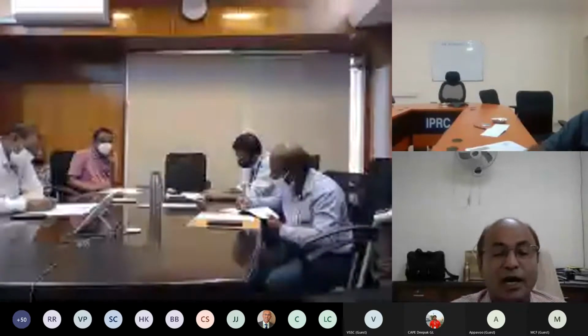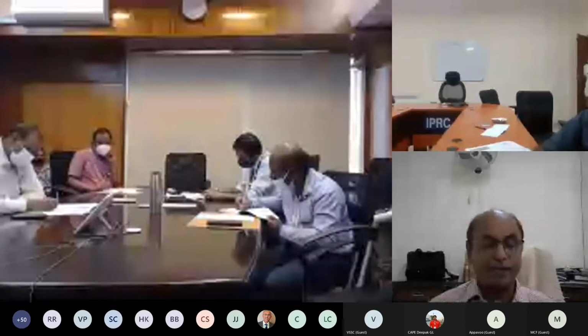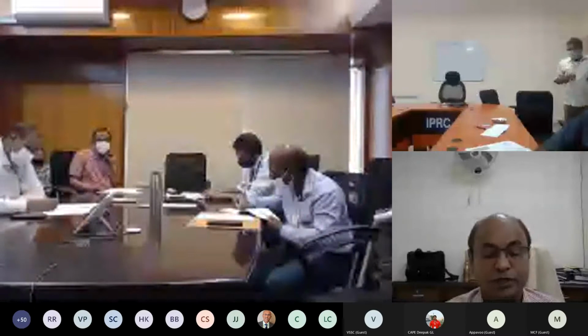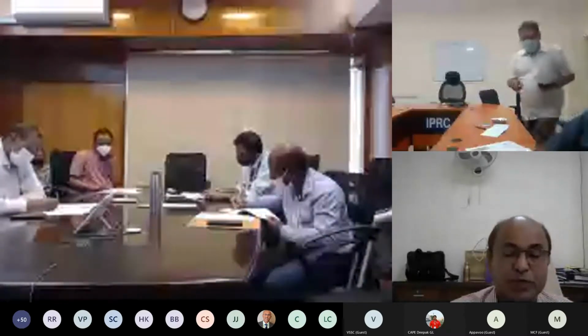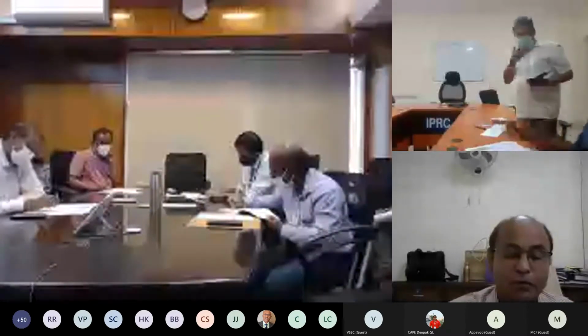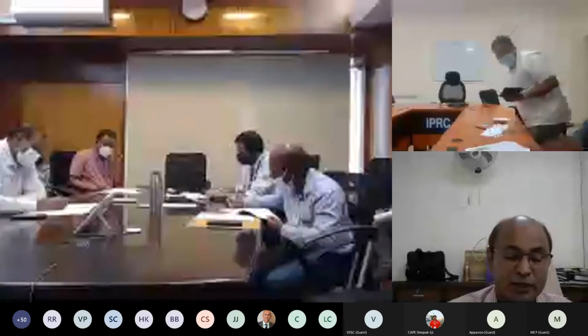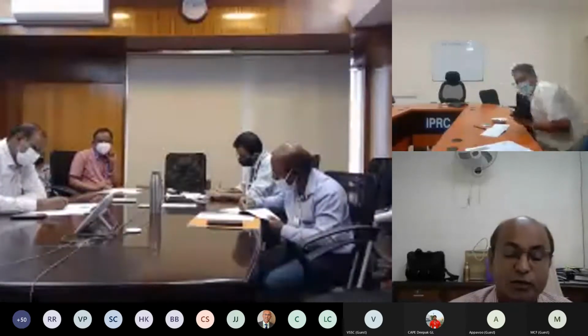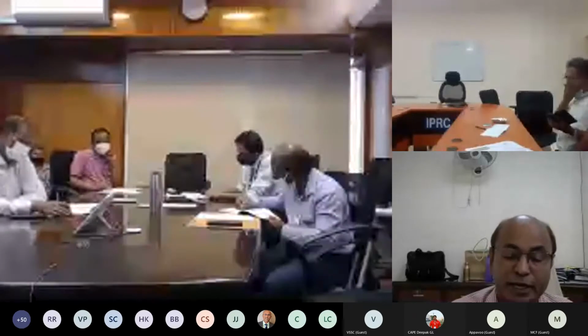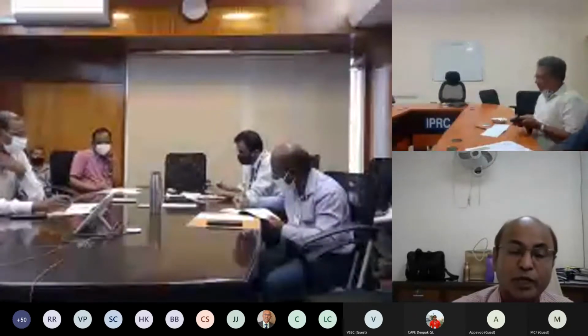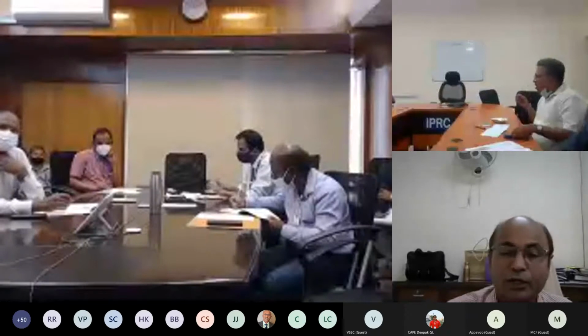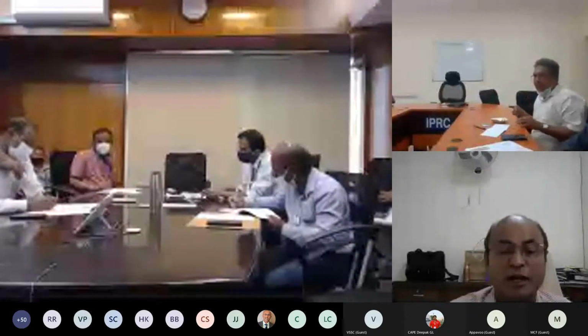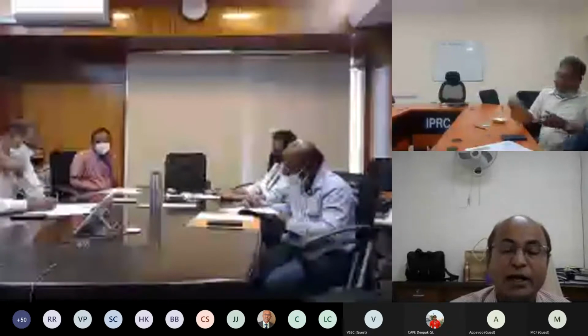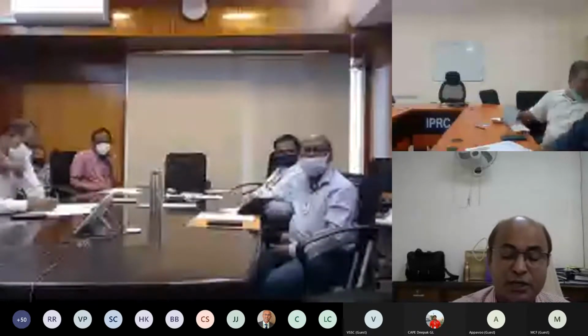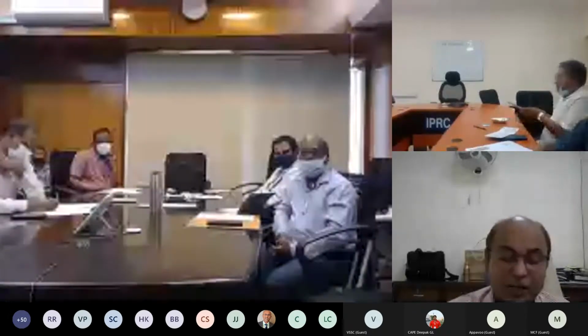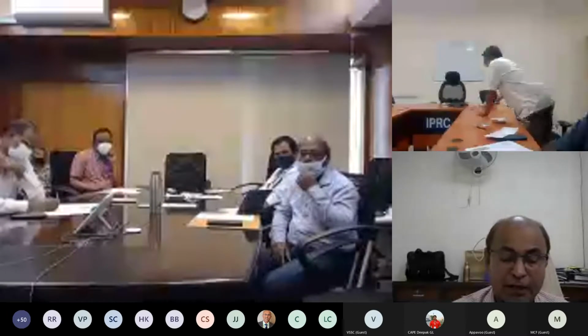In the end, I would like to urge every engineer and technician to follow the safety regulations in letter and spirit. Take proper permit of work before starting any maintenance work. Ensure that the section on which maintenance is being carried out is isolated from both ends. Not only should it be isolated, but it should be temporarily earthed from both ends to avoid residual charge or accidental charging or switching.